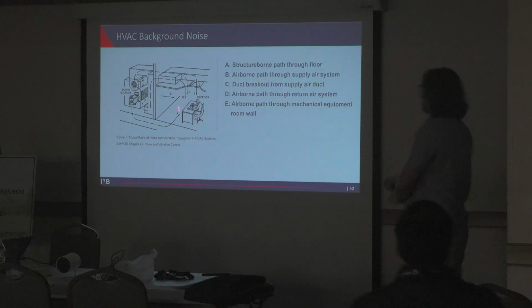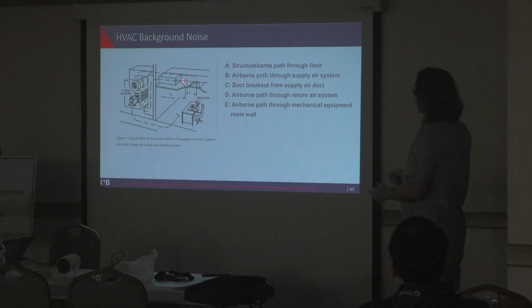In this one, it's got a mechanical wall, so that adds this path, but that's not always there. What we'll always look at is the supply noise, the noise literally that comes from the unit in through the diffuser. We look at noise that comes from the unit, breaks out the duct before it gets to the diffuser in cases that the duct runs completely overhead. We look at the return path, and we look at structure-borne vibration isolation, and we also look at mechanical room walls and things like that.